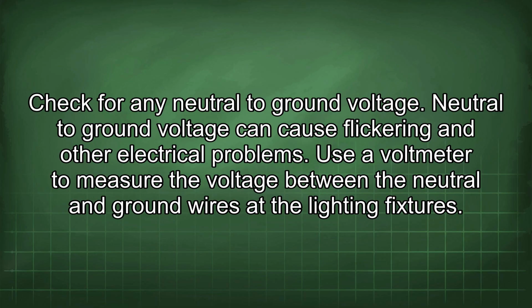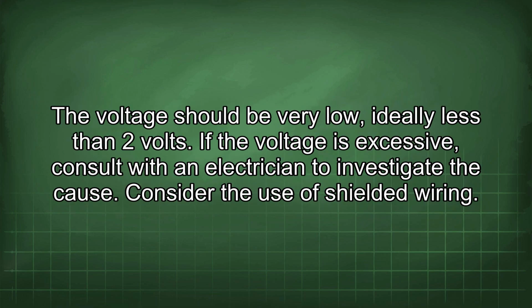Check for any neutral to ground voltage. Neutral to ground voltage can cause flickering and other electrical problems. Use a voltmeter to measure the voltage between the neutral and ground wires at the lighting fixtures. The voltage should be very low, ideally less than 2 volts. If the voltage is excessive, consult with an electrician to investigate the cause.